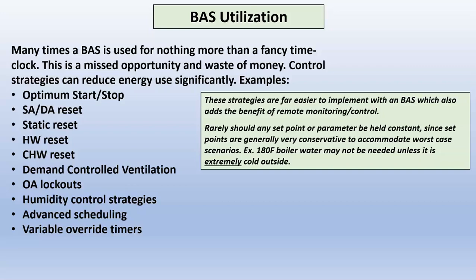Same way with hot water reset, instead of leaving it at 180 degrees all year, well, when it's really warm outside, or starting to warm up, I should say, I should lower that. I don't need 180 degrees when it's 50 outside instead of 20. Chill water reset, same story. When it starts getting colder, I don't need 42 degree air, especially humidity can affect this also. If it's not real humid, it's starting to cool off, I could use some hotter air, hotter chilled water temperature.